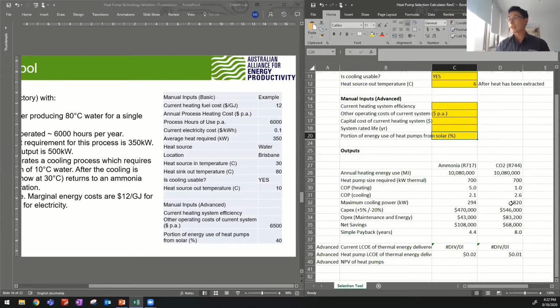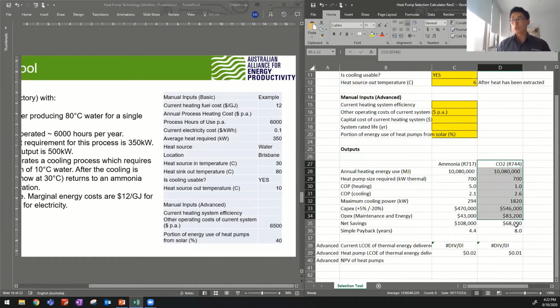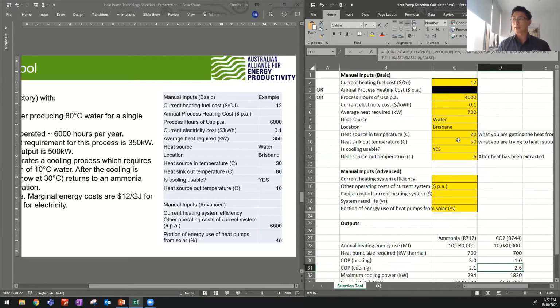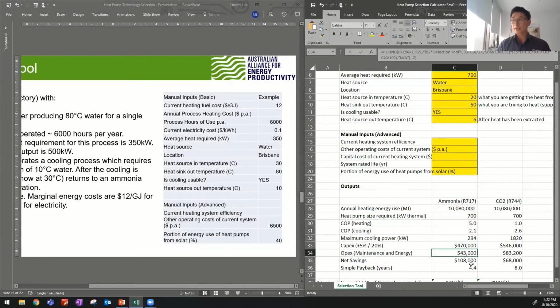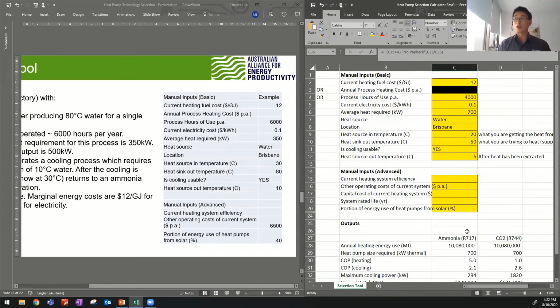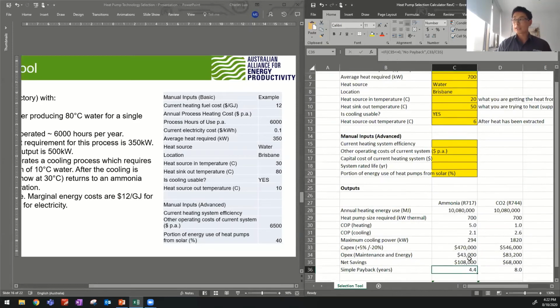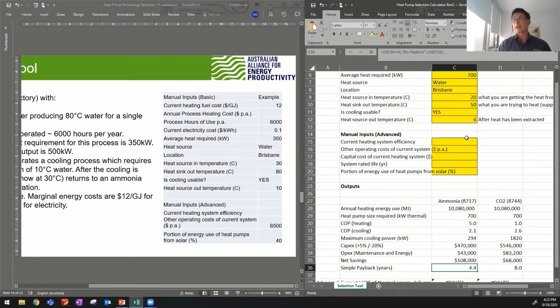And you can straight away see in an aquatic center, you wouldn't go with CO2. That is the wrong refrigerant to use for these sort of temperatures. An ammonia system would give you fairly good payback if you just straight up replace an old school boiler system, because it can supplement that cooling for your HVAC. So that cooling could be used to dehumidify the pool, for example.